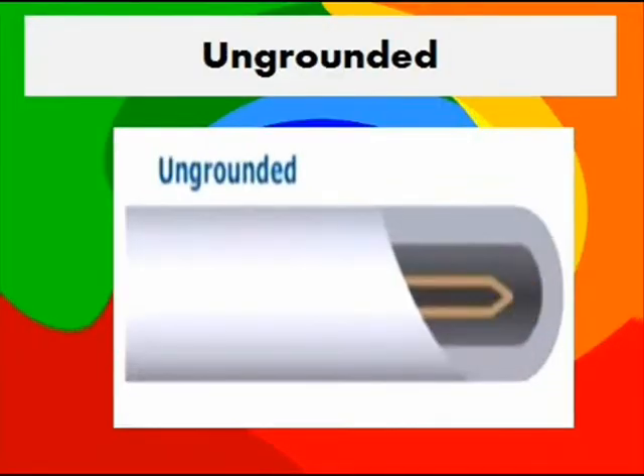Okay, commercial thermocouples take the form of a probe with the measuring junction housed in the tip. There are three main types of measuring junction. First is grounded, ungrounded, and exposed. Okay, now let me show you this picture, where the picture shows grounded, ungrounded, and exposed. Can you see the difference between the grounded, ungrounded, and exposed by the picture only? Yes, you can. But now let me explain in more detail the difference between these three types of junction.